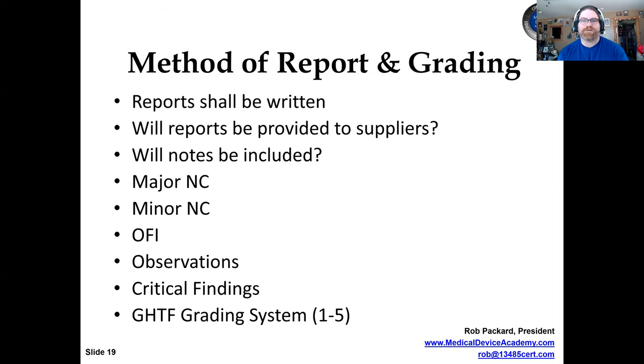The grading of findings: traditionally we'd have major findings, minor findings, and opportunities for improvement, or OFIs. However, the notified bodies and certification bodies under the MDSAP program and GHTF guidance have switched to a numbered system where you get points, up to 6 points issued, but the scoring system goes from 1 to 5, 5 being a serious major nonconformity, though they don't call them majors - they just call it a score of 5. You could simulate that system, but it's not required.